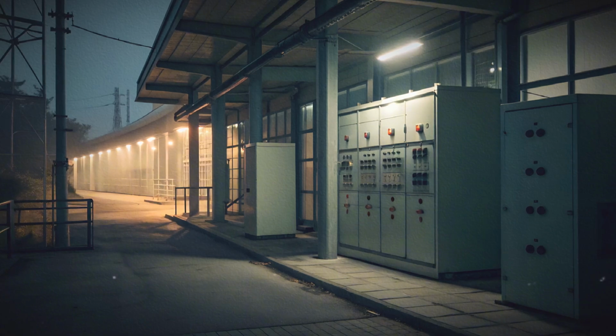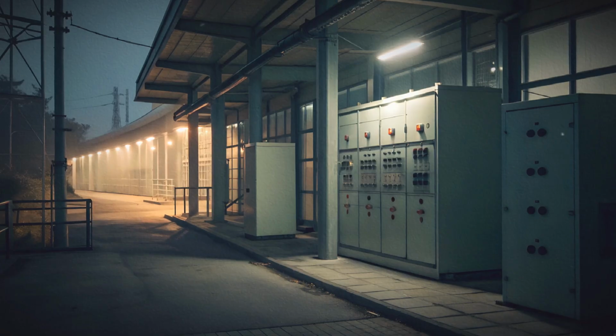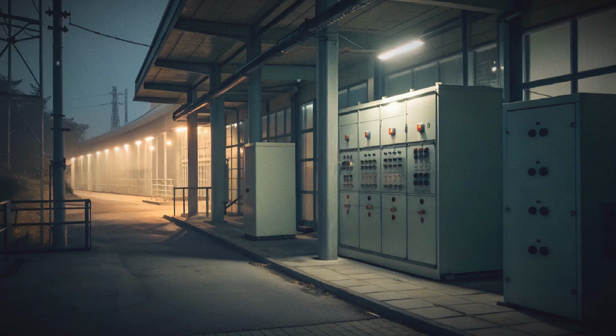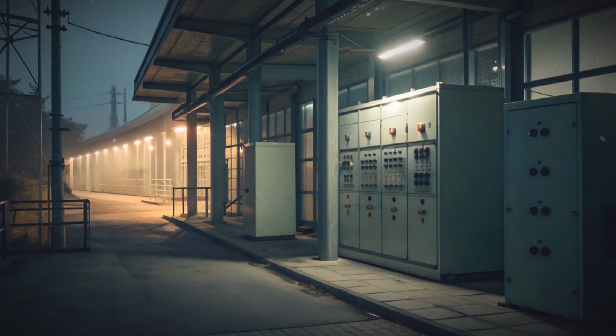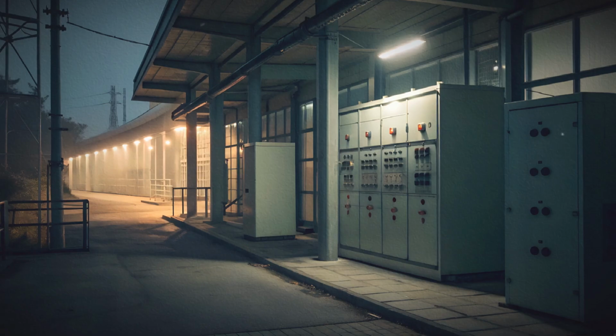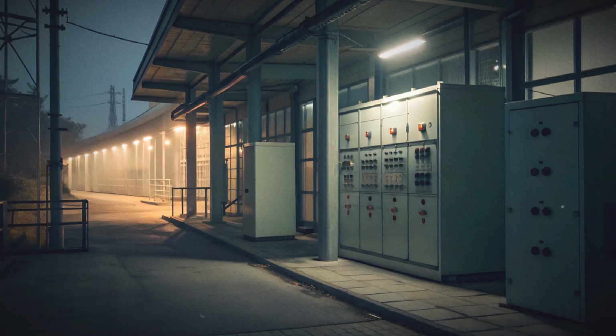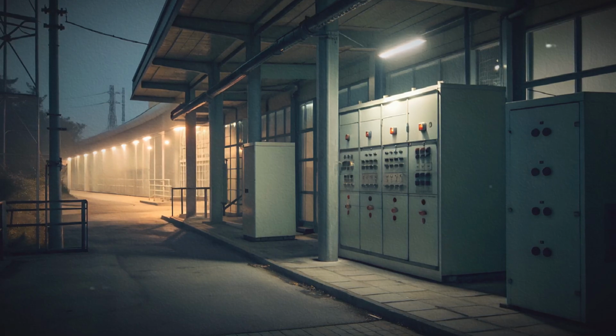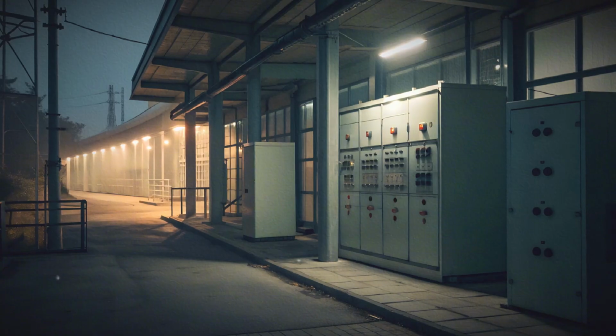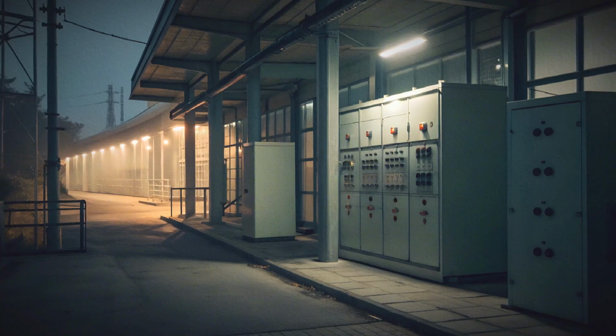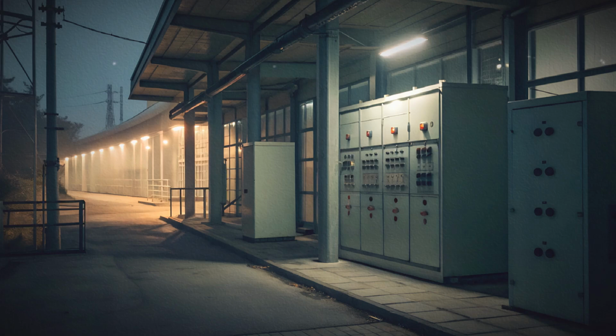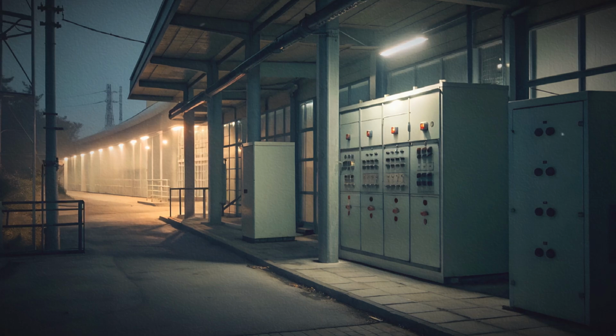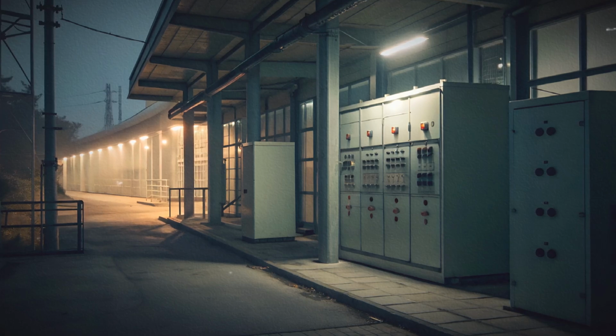Maintenance and testing maintain the reliability of protection systems. Protective relays are tested for correct settings and response. Circuit breakers undergo timing tests and condition assessments. Communication links used for pilot protection and for PMU data are verified. Protective coordination studies are updated when system changes occur, such as new lines, new generation, or changes in operating patterns.